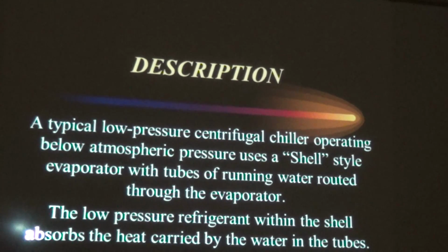What is Type 3? It is a low pressure centrifugal chiller operating below atmospheric pressure, using probably a shell style water box, evaporators, and what happens is that we study here, and this test is about mechanical compression air conditioning, not chemical absorption air conditioning. A chiller is a mechanical compression air conditioning system. The only difference is there's a whole other set of pumps that's used.